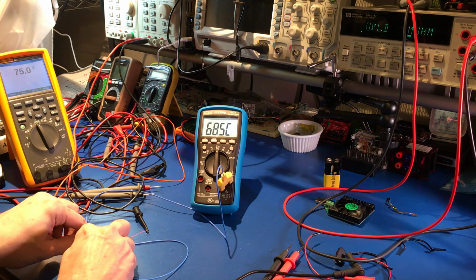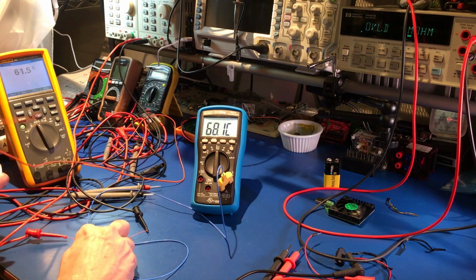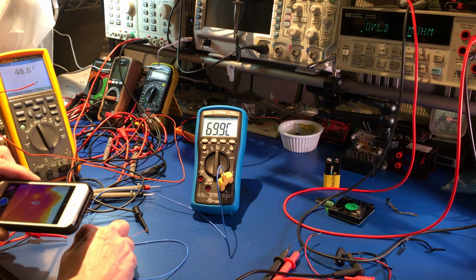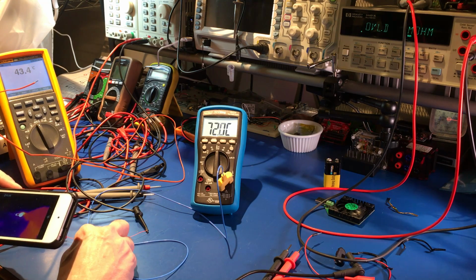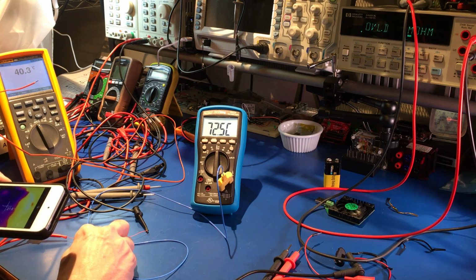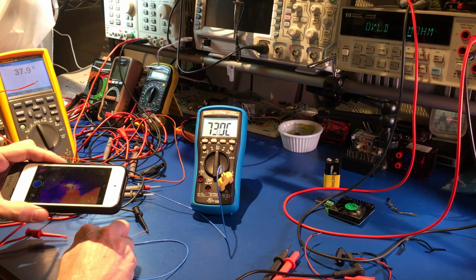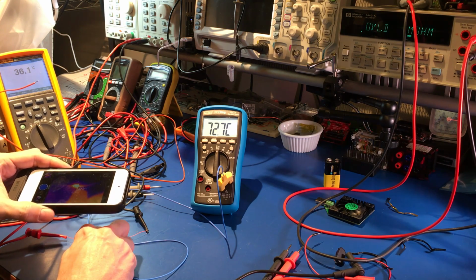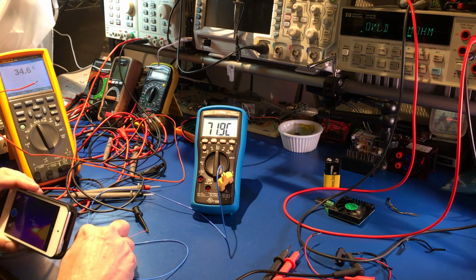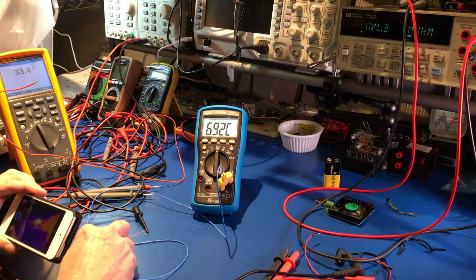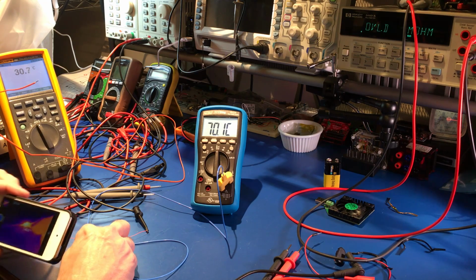Very responsive on the BM235 Brymen, for it to see that on and off drop of current and change the temperature that fast. I like that. That was nice. I'm actually very impressed with the temperature reading on this Brymen right now. I'll remove the Fluke probe, so we'll just be reading it with the Brymen, and I'm down to about 9 milliamps of current drawing on it, which says it should be at about full temperature. And here's where I'm having the problem, because I got that reflective surface, and I got to get my FLIR at the right angle to compare it. I'm picking up 69.4.